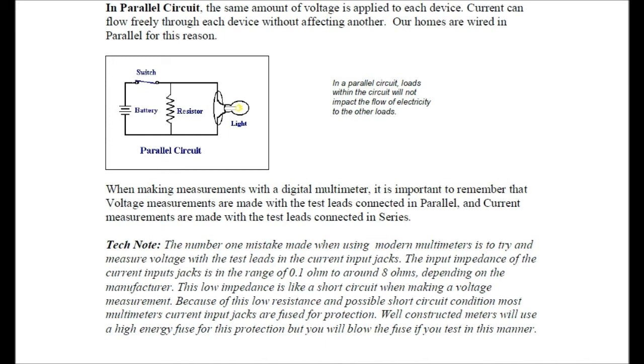Tech note. The number one mistake made when using modern multimeters is to try and measure voltage with the test leads in the current input jacks. The input impedance of the current input jacks is in the range of 0.1 ohms to around 8 ohms, depending on the manufacturer. The low impedance is like a short circuit when making a voltage measurement.